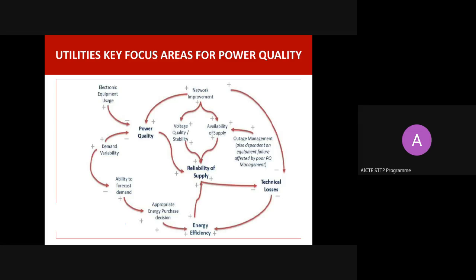Again, if power flows in a circuitous path, we have to redraw the network. We have to reinvest, investing more to create a new network to ensure power flows in the shortest path. Thereby, network improvement: by increasing the capacity of the transformer, increasing the capacity of the conductor, and putting appropriate devices at appropriate locations, we have to create more network. With more network improvement, power quality will increase, power stability will increase, and the availability of power supply will increase. So network improvement is the first factor the utility has to take care of to improve the power quality.